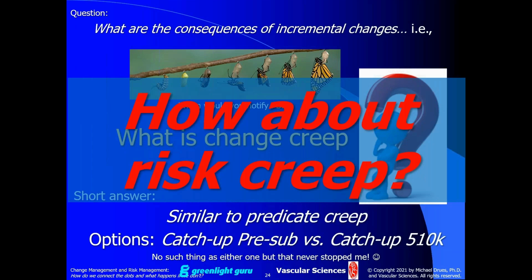This is something that we don't hear many people, at least I haven't heard people, talking about in our medical device industry. It is a phrase that's used in some other industries, but I haven't seen it. Perhaps in the discussion, John, you can correct me if you've seen this phrase, risk creep. But with all of the changes that we make to our medical devices and their associated changes in risk, do we risk, pardon the pun, experiencing risk creep?